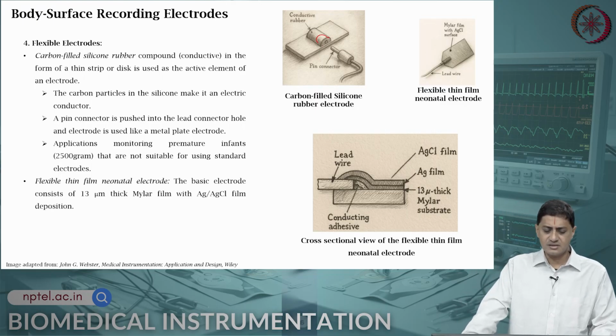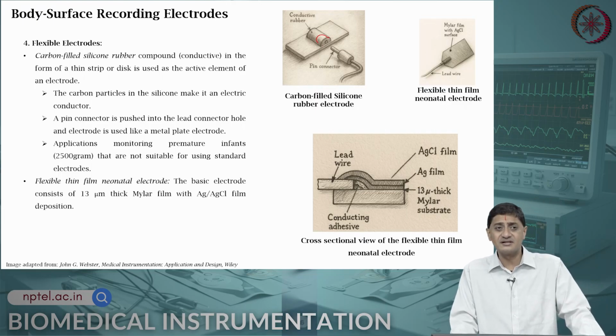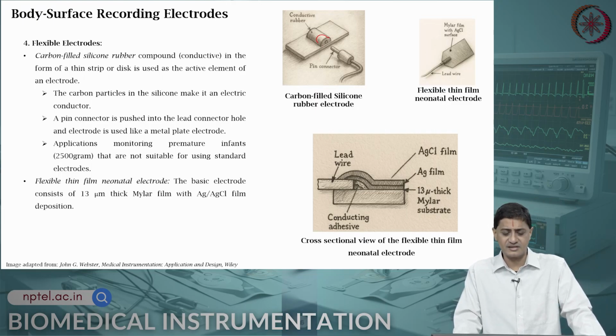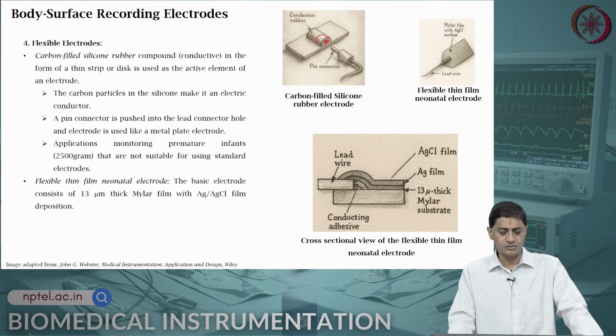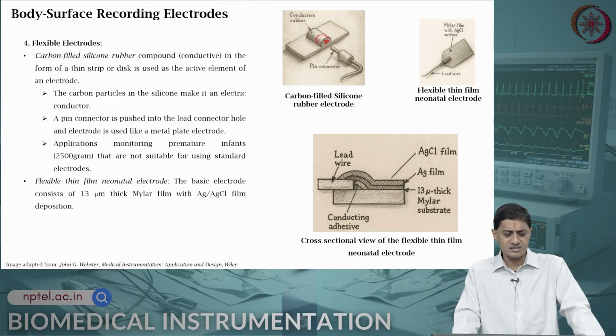Now, the carbon particles essentially act as the conductor, act as the electrode, and the pin connector is pushed into this hole here to make it equivalent to a metal electrode. What are the applications? The applications of these involve essentially monitoring of infants, usually premature infants who weigh below 2.5 kgs, for whom we cannot use standard electrodes.